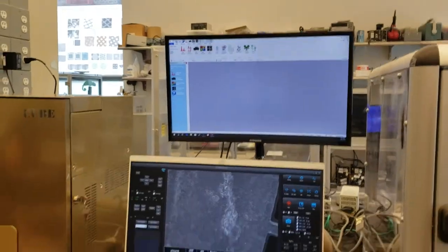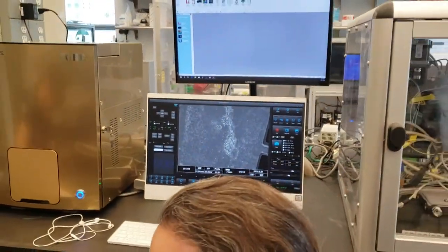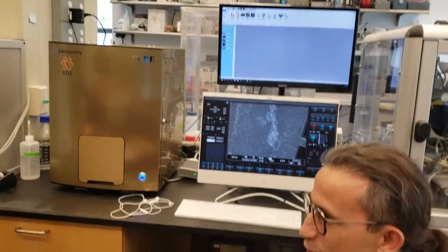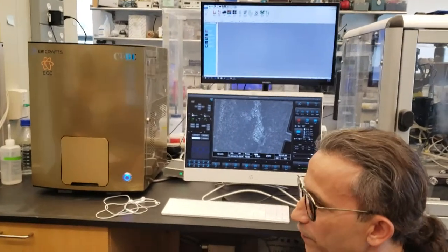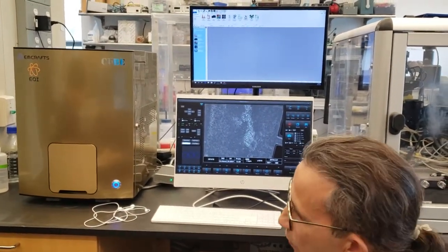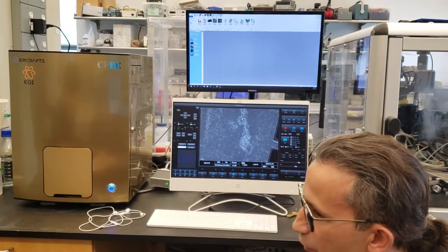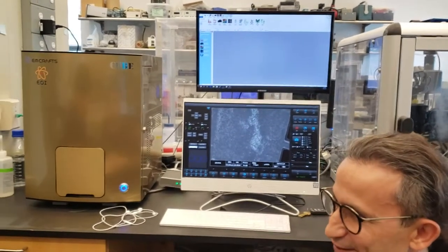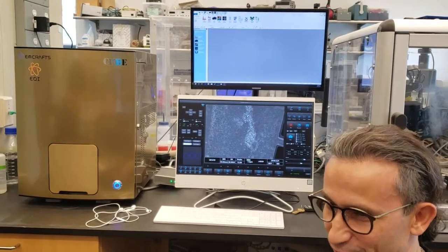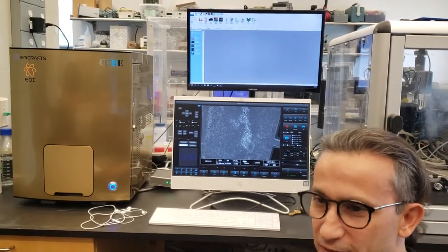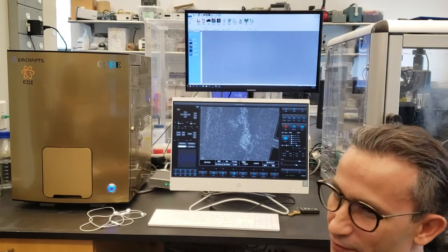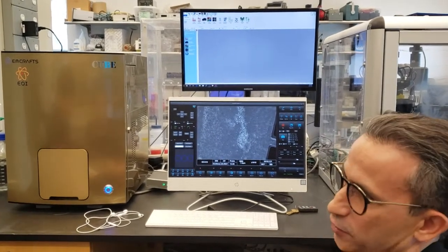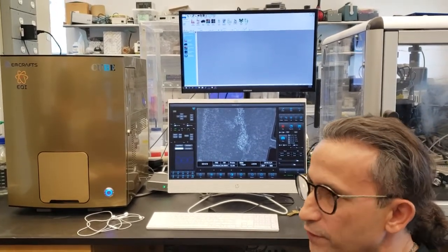If we're doing X-ray maps, and I keep jumping around to these X-ray maps, because these are important things. When you start doing X-ray maps, you want to look at the information faster. So we don't need to look at it at 4 microseconds, because we're really not looking at spectral peak resolution. We're looking at pixel information. If we're colorizing a pixel, color red for aluminum, we're just looking at it, it's red, it's aluminum. So let's just process the information really, really fast.